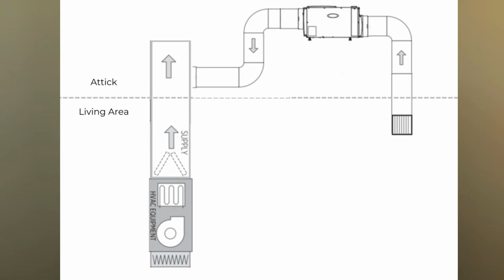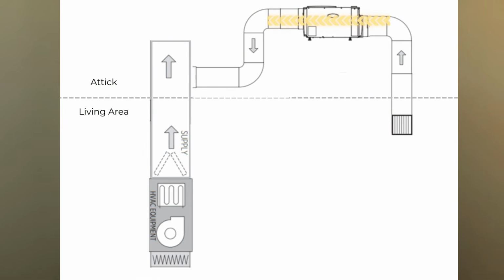And the third way is for upflow systems that are typically found in closets. Just like in example 2, the output duct is run directly into the supply plenum of the central AC system. And since there's little to no room for the dehumidifier inside the closet, we typically have to install it in the attic. And since there's little to no room in the closet, we typically can't run a return air duct to the central AC system. So we install a new return air duct that is independent for the dehumidifier, and we normally install the new return air duct in a common area of the home.